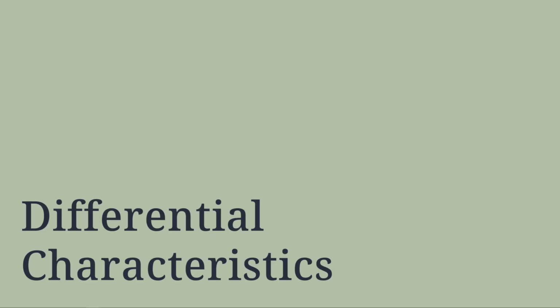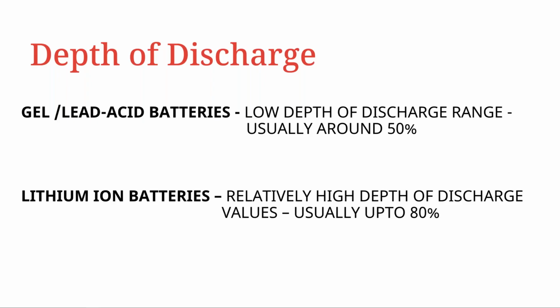So what are the differential characteristics? First, the depth of discharge. Typically for gel or lead acid based batteries, you have a low depth of discharge range, usually around 50%, whereas with lithium ion batteries you have a relatively high depth of discharge, usually up to 80% or more, depending on the brand and utilization of the battery.